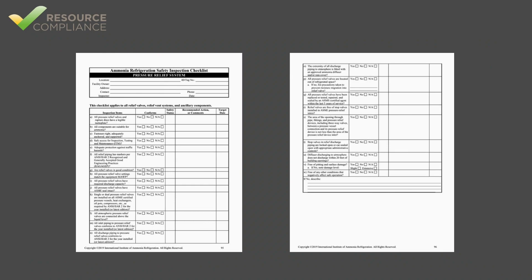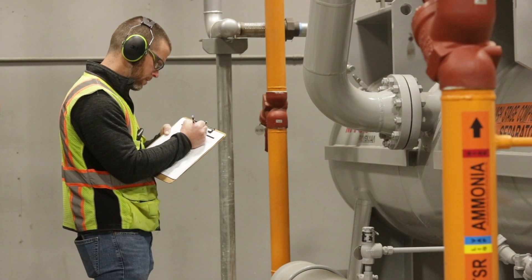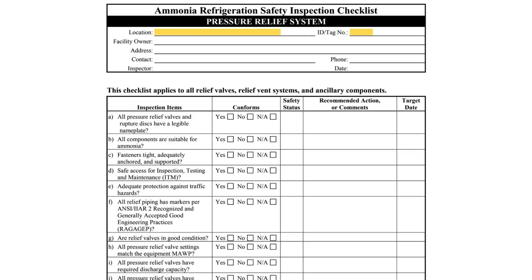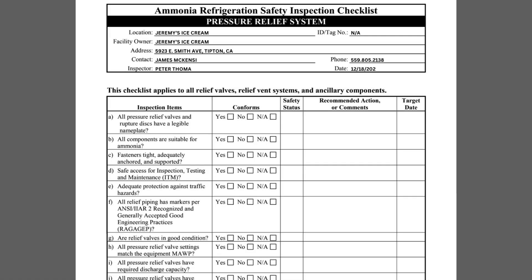The simplest part of completing the Pressure Relief System Checklist is filling out the contact information. Each IIAR 6 checklist requires the inspector to indicate the location, owner, and physical address of the system. The contact's name and phone number should be the facility representative responsible for ensuring the inspection is completed. Additionally, the inspector must write his or her own name and the date of the inspection. The ID or tag number belongs in the upper right corner. Pressure relief systems are not always given a unique ID or tag number, so NA is often indicated here.